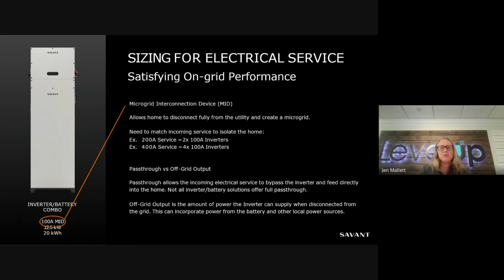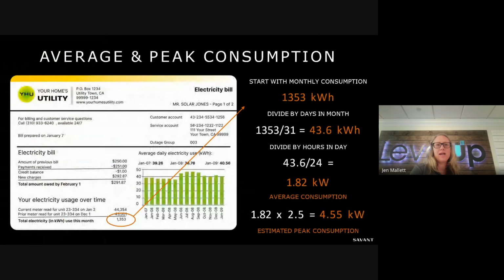We also talk a little about pass-throughs, which means bypassing an inverter to feed directly into the home. Not all inverter and battery solutions offer full pass-through, so that's something to consider. This last line is really important: off-grid output is the amount of power the inverter can supply when disconnected from the grid, and this can incorporate power from the battery as well as other local power sources like generators. That's really how we start when looking at sizing.